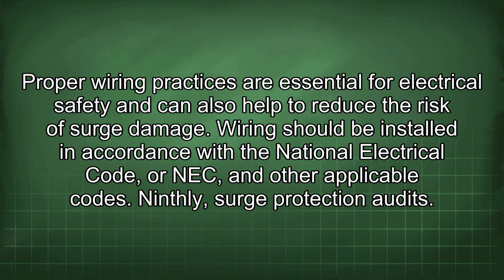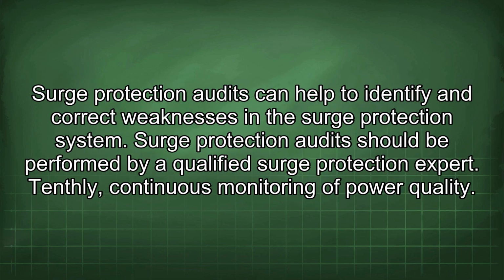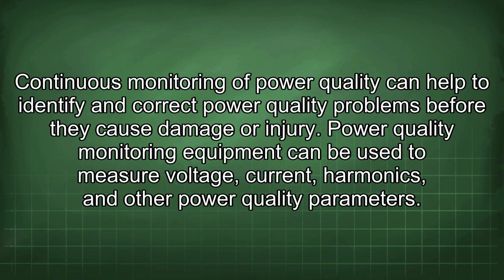Ninthly, surge protection audits. Surge protection audits can help to identify and correct weaknesses in the surge protection system. Surge protection audit should be performed by a qualified surge protection expert. Tenthly, continuous monitoring of power quality. Continuous monitoring of power quality can help to identify and correct power quality problems before they cause damage or injury. Power quality monitoring equipment can be used to measure voltage, current, harmonics, and other power quality parameters.